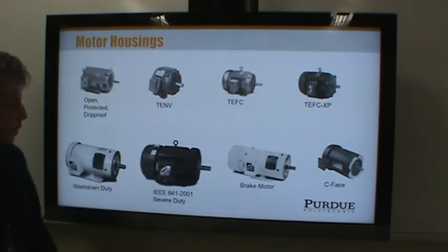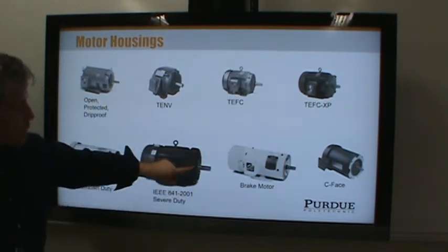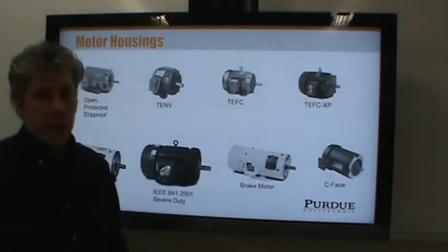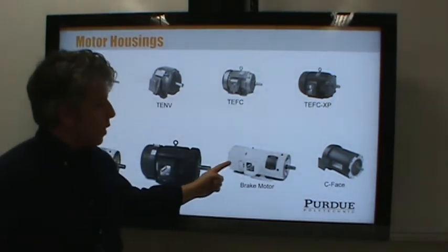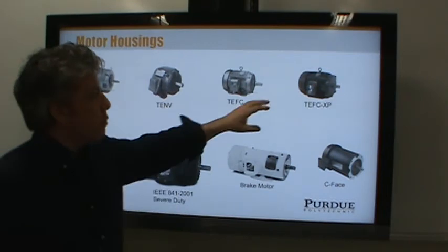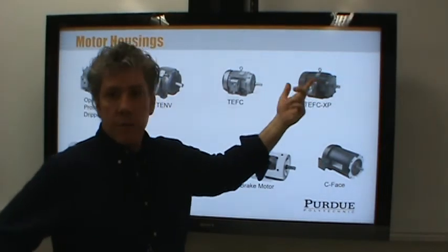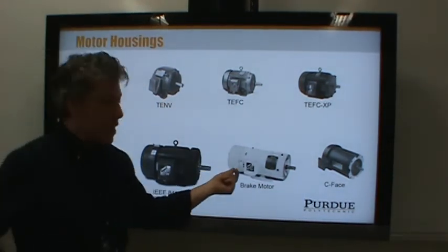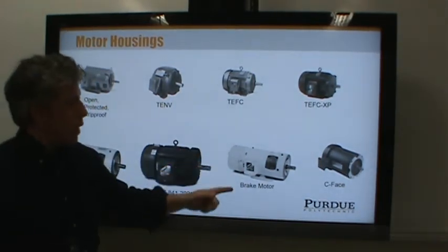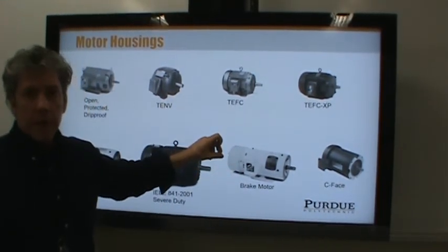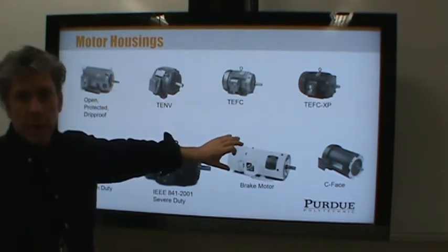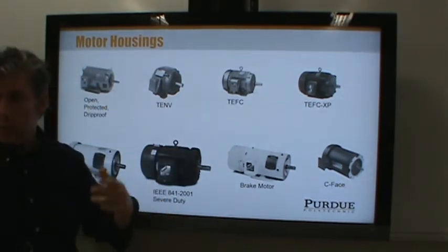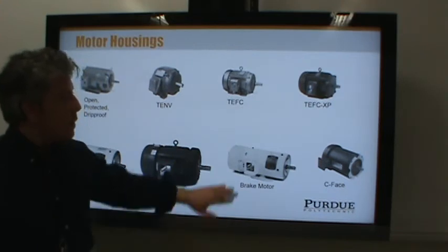Here's a severe duty motor — notice it has fins even on the face to get as much heat out as possible. A brake motor has a brake on the back, which is extended. Most motors will coast to a stop when power is removed. A brake motor has several options: some brakes require activation via extra wiring, others are mechanically driven by a centrifugal switch that activates the brake as the motor slows down.